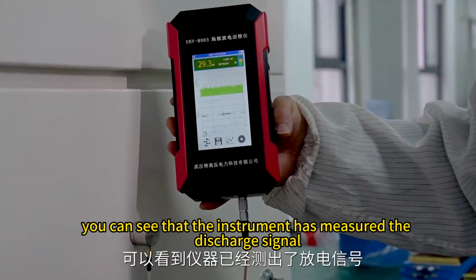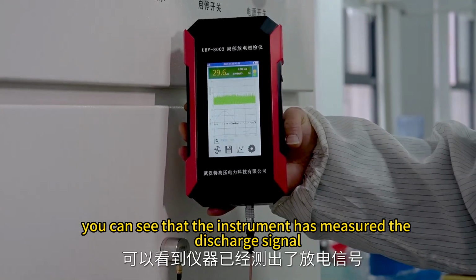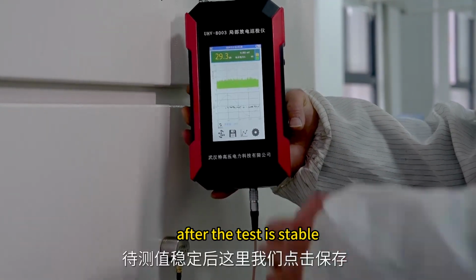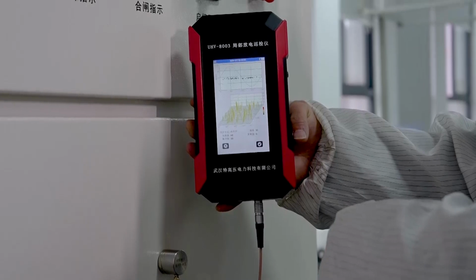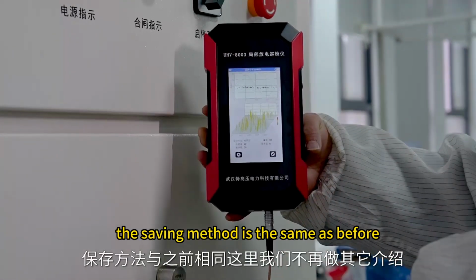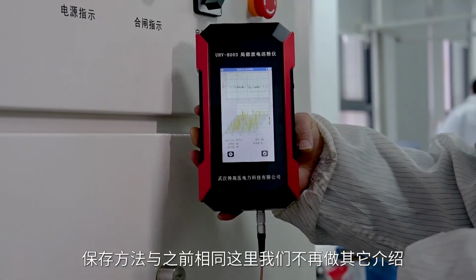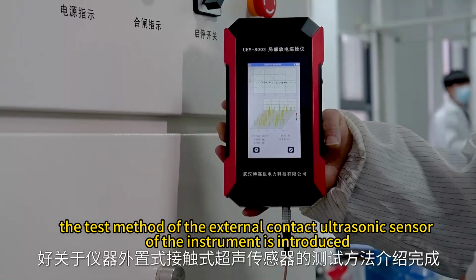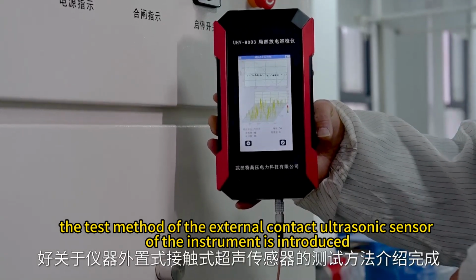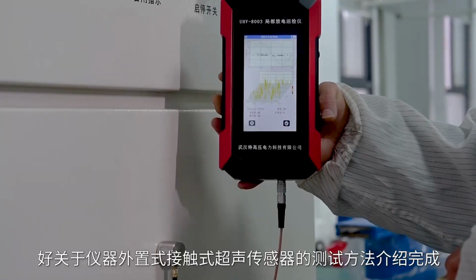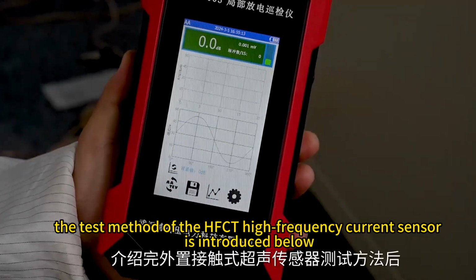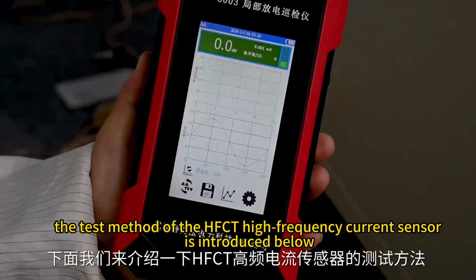You can see that the instrument has measured the discharge signal. After the test is stable, click Save here. The saving method is the same as before. The test method of the external contact ultrasonic sensor of the instrument is introduced. The test method of the HFCT high-frequency current sensor is introduced below.